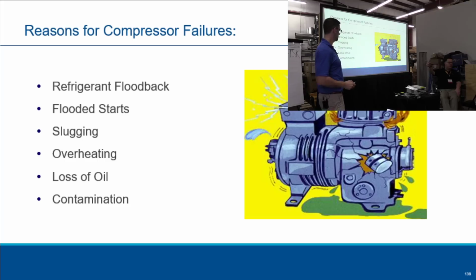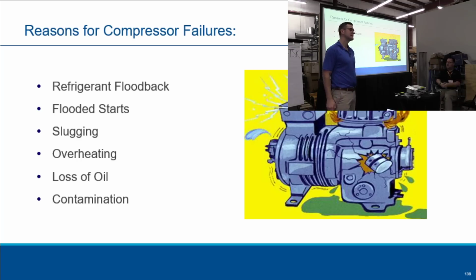Just the one point I want to make, to wrap your head around that compression ratio, for those that walked in that didn't know how to do it: the number one killer of compressors, by far, it's not even close, is overheat. And the number one reason for overheat is compression ratio. As Trevor said, the farther those numbers get apart, the hotter it gets. Your discharge gas is not where it should be.